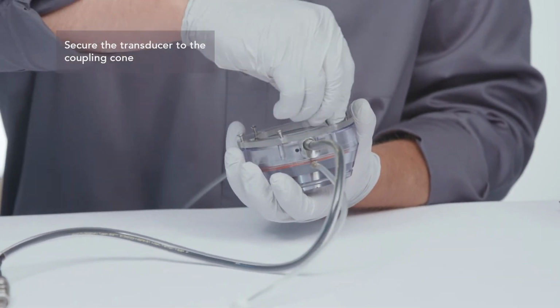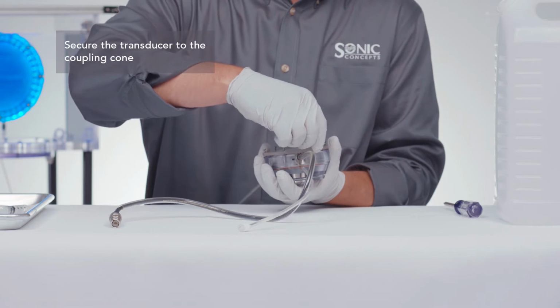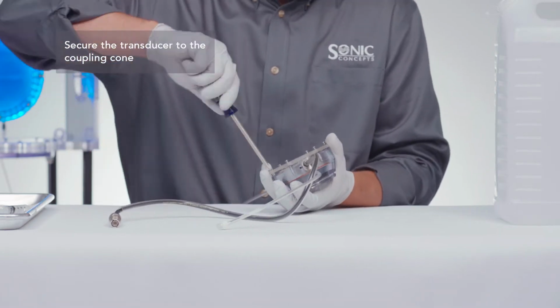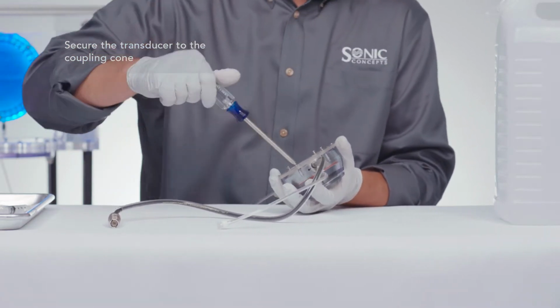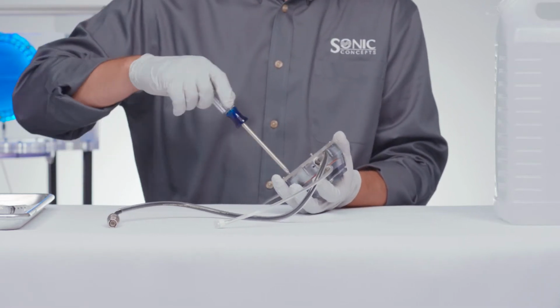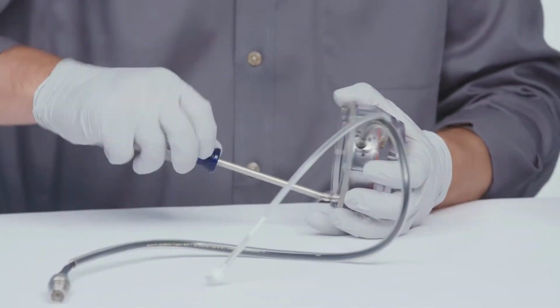To secure the cone in place, apply the adapter ring to the rear of the cone and transducer assembly. Tighten all 6 Phillips flathead screws using a star pattern sequence until hand tightened.